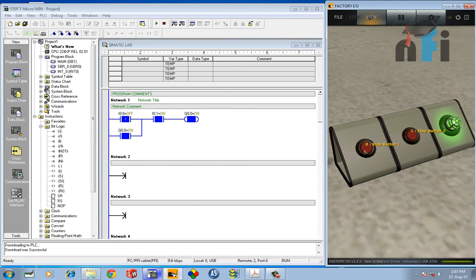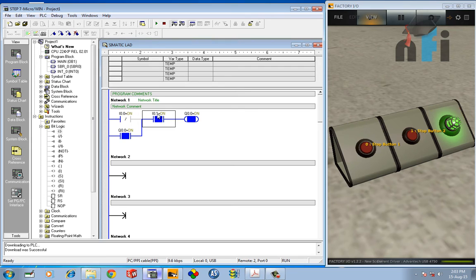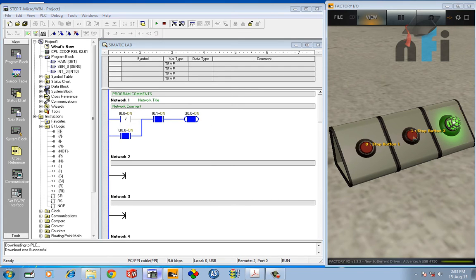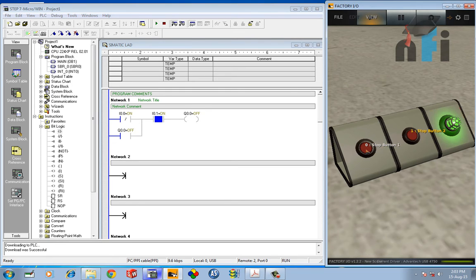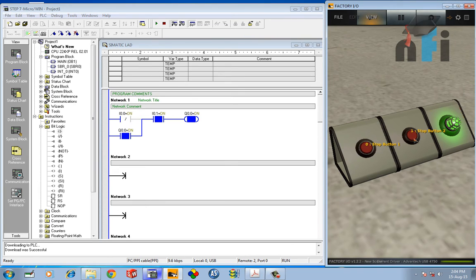Output is latched. So when I press this button which is linked to this contact, this will be false. You must focus on the addresses. This is the address of this button, that's the address of this button. So this will be unlatched. This one is latched and this is unlatched. So that's how you can do latching and unlatching using two NC buttons.